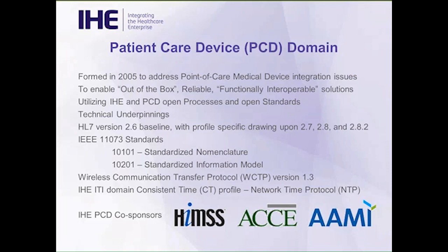We also make use of IEEE 11073 standards, more specifically 10101 for standardized nomenclature and 10201 for standardized information model. The IHE ACM profile, Alert Communication Management, also makes use of the Wireless Communication Transfer Protocol, WCTP, at version 1.3. As all of the PCD profiles need consistent time, we also make use of the IT Infrastructure profile, Consistent Time. Most people recognize this as use of the Network Time Protocol.